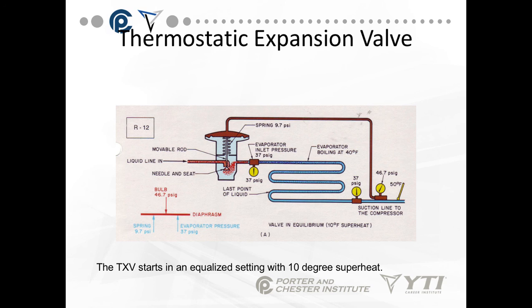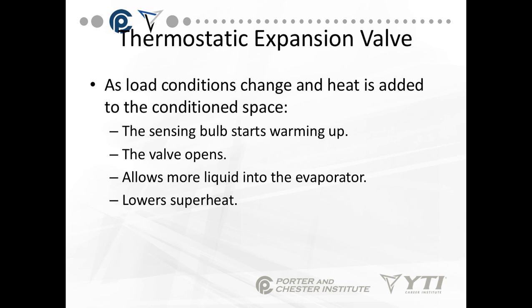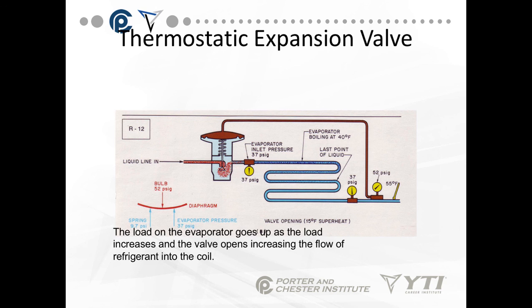Here's an example starting with an equalized setting at 10 degrees superheat using R12. The system is running normally — the bulb pressure is pushing down with 46.7 PSI, and the spring and evaporator pressure are pushing up with the same force, so we're at equilibrium. As load conditions change and heat is added to the conditioned space, the sensing bulb starts warming up, the valve opens and allows more liquid to the evaporator, and lowers the superheat. Now the bulb pressure is at 52 PSI pushing down, while spring and evaporator pressures are still at 46.7 PSI, so the bulb pressure has pushed the needle down and is allowing more liquid refrigerant into the evaporator.